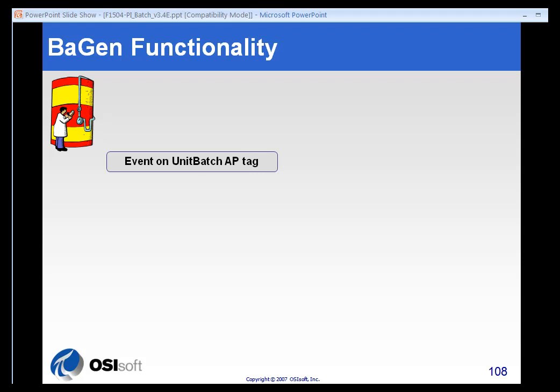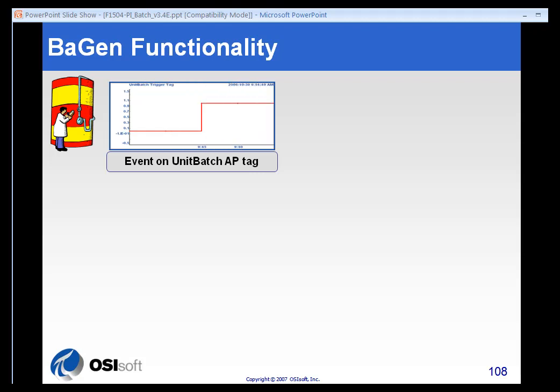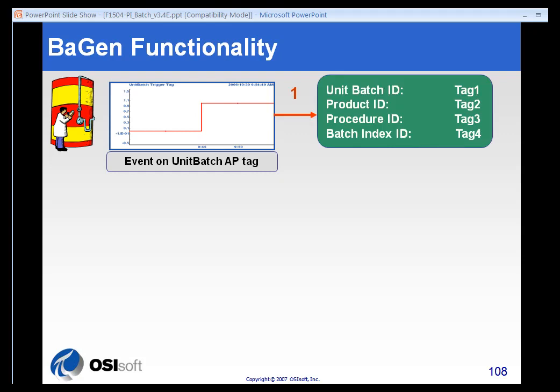Everything in the batch database is triggered at the unit batch level. Let's first look at the unit batch and subsequent PI batch configuration in terms of the PI batch generator. There is some event that triggers the start of the batch — this is usually referred to as the active tag or the trigger tag — and that tag will change its state to indicate that the batch has started.